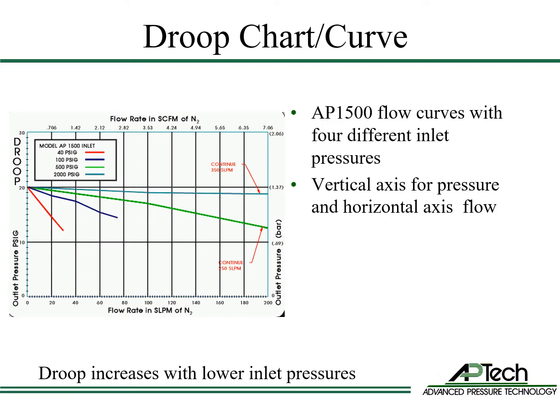This is a typical droop curve, or flow curve. At the top, it indicates the gas used — in this case, nitrogen. Flow curves plot outlet pressure on the vertical axis and flow on the horizontal axis. The bottom left of the chart is zero flow and zero pressure. This AP1500 regulator flow curve demonstrates the impact of four different inlet pressures with a 20 psi fixed zero-flow outlet pressure setting.